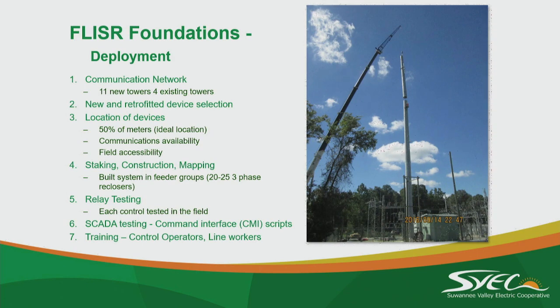We were doing 20 to 25 reclosers a year out in the field. Once you deploy, we did relay testing. We tested each relay in the field with an Omicron, made sure the relay was programmed and ready to go in the field, and that everything made it, all the wires were in the right spot.